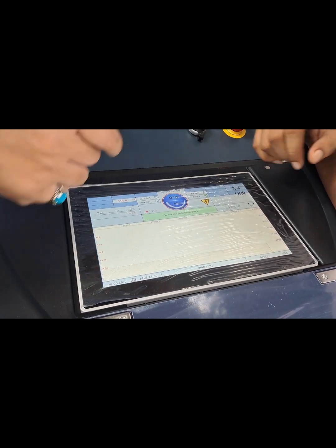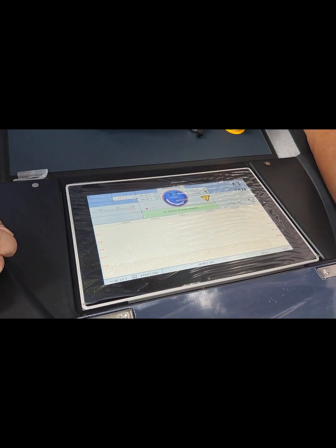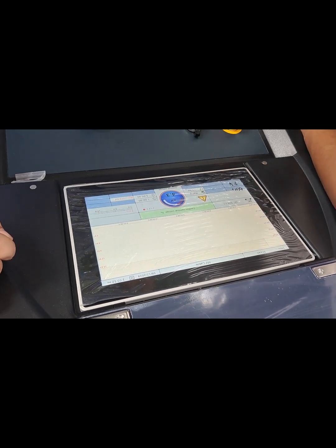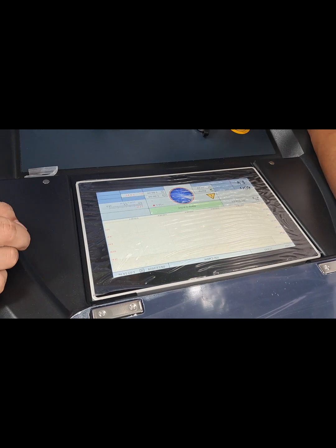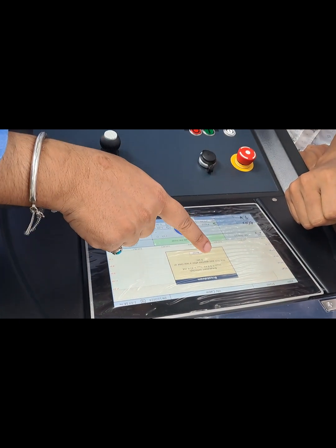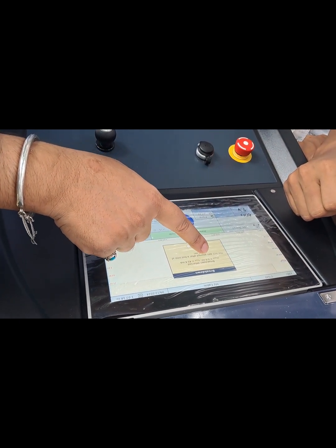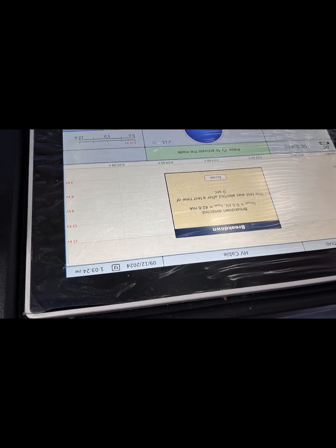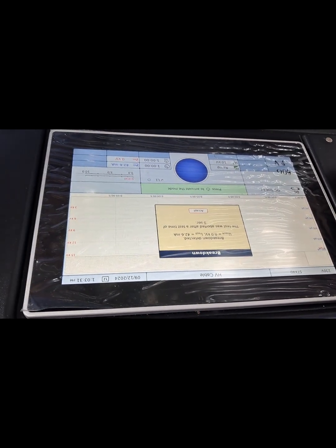Now it will ask how much voltage you have to inject. I think this is enough. Okay, enter. Accept. Breakdown. Your breakdown is 0 kV. Fault current is this. This is showing the short circuit. Breakdown level is 0 between voltage and current. But you will get a graph, no problem.